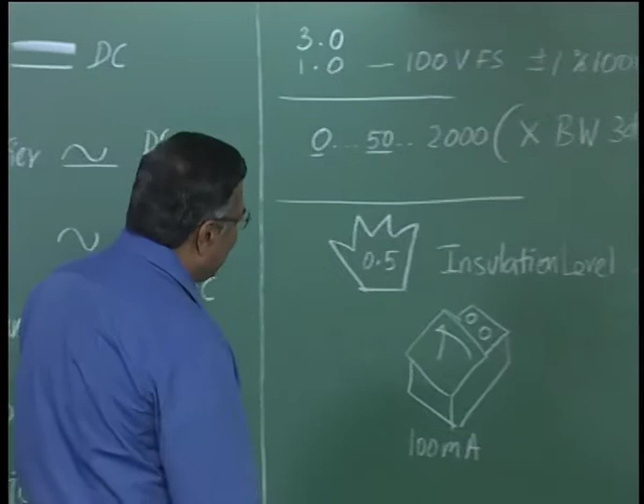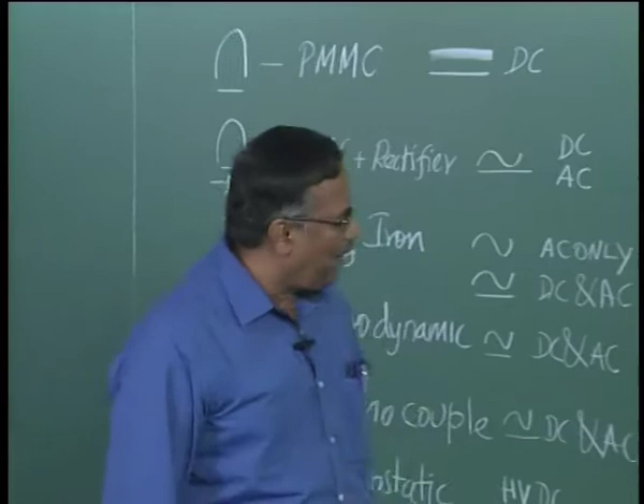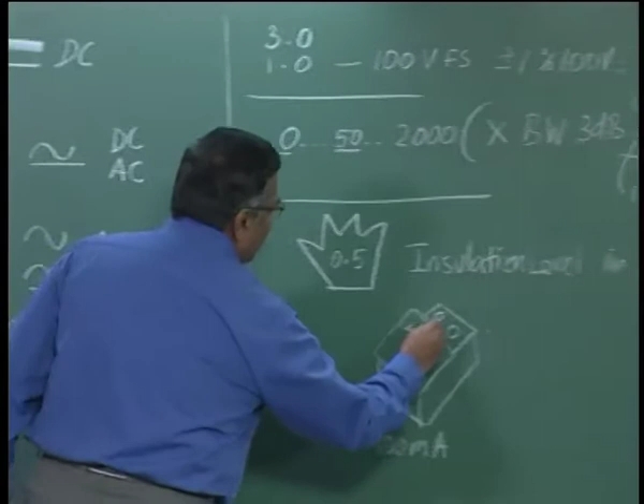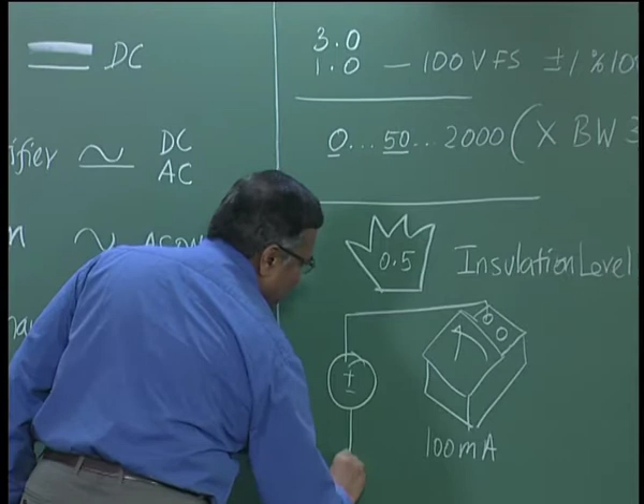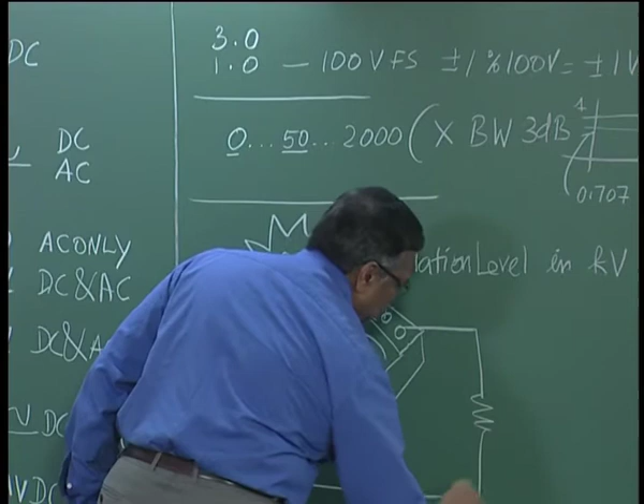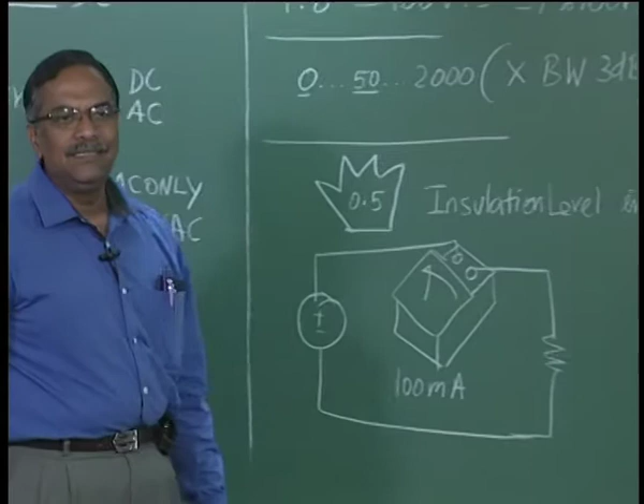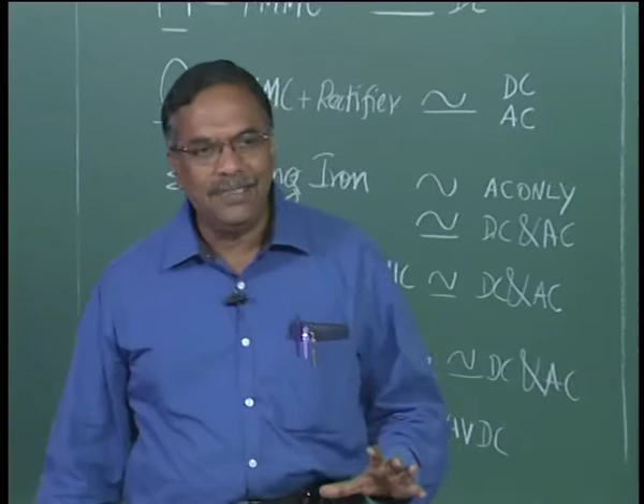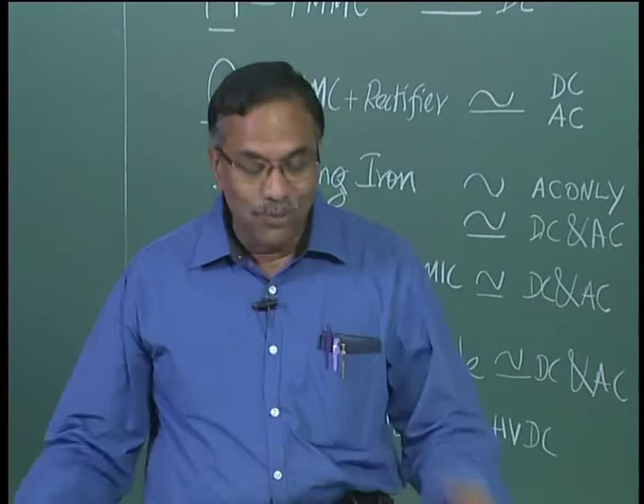What he says is that any terminal of that meter with respect to the body can at the maximum go to 500 volts, right. So if I am going to use it on a table, I put it on the table and connect it to a voltage source, it could be DC or AC, it does not matter, and then I connect the load, right. This voltage, because it is going to be on this terminal as well as on this terminal, can at the maximum be 500 volts, right. It is the same with voltmeters, it is the same with wattmeters. The insulation level of the meter talks about the insulation breakdown voltage between the casing and the terminals, right. It has nothing to do with the type of meter that you have, okay.